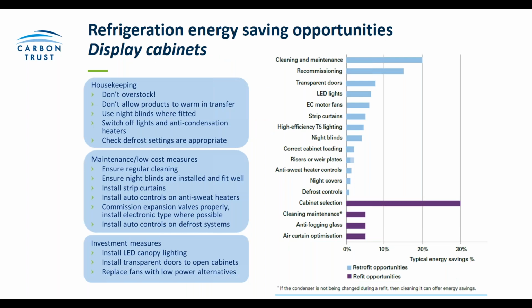So in terms of housekeeping, it's really important to make sure your cabinet isn't overstocked and make sure that the air grills are clear of product and merchandising. A properly stocked cabinet will maintain optimum food temperature with minimum energy consumption. That's what you're aiming for. It's also important to make sure the product loaded into your cabinets hasn't warmed up by being left in an ambient temperature area. When the shop is closed, use any night blinds and covers and switch off lights and anti-condensation heaters as well. If you have got lights under shelves, consider whether these can be switched off or maybe even removed. They might not be necessary.